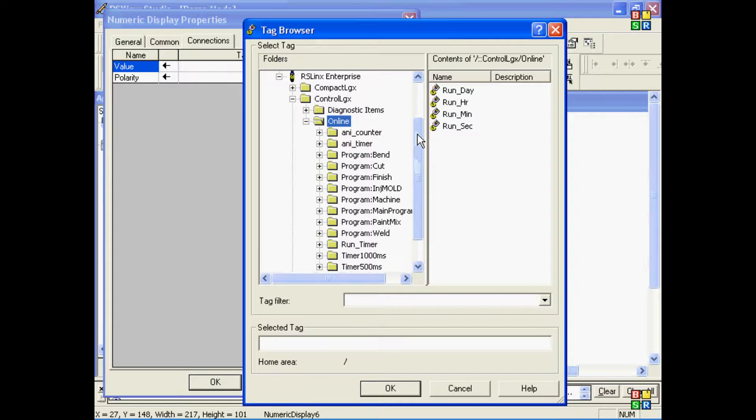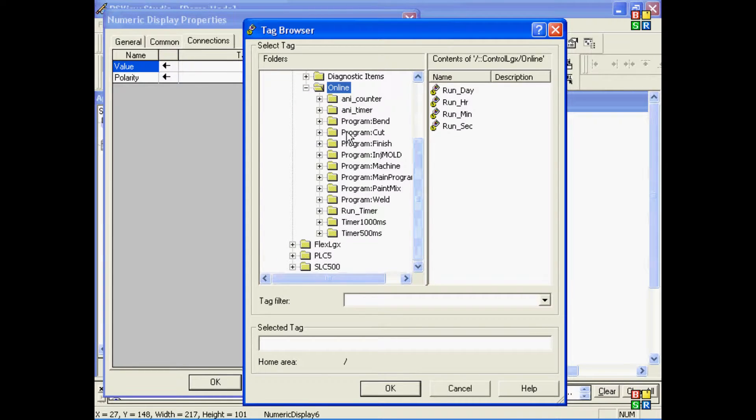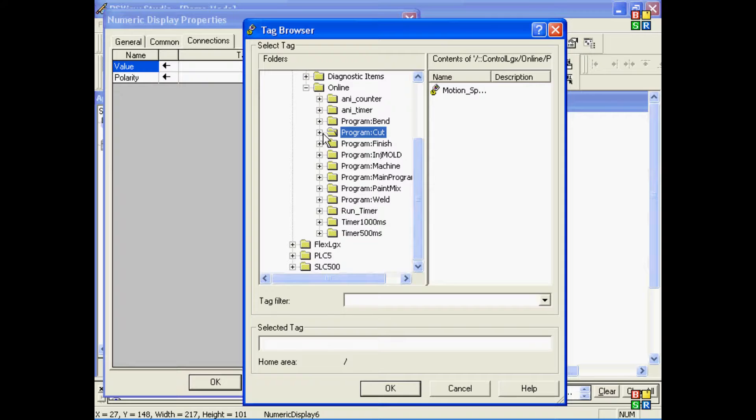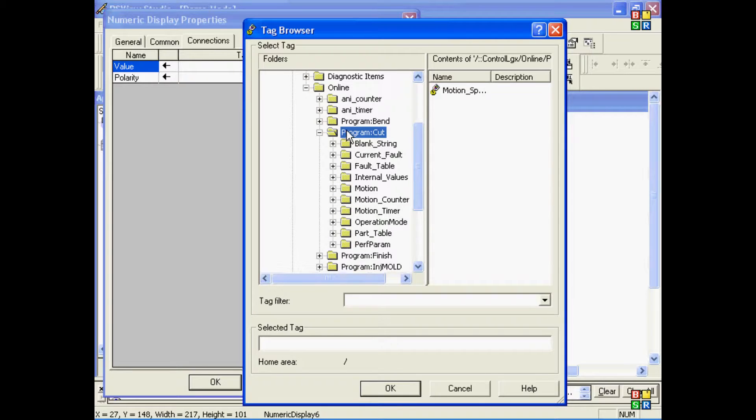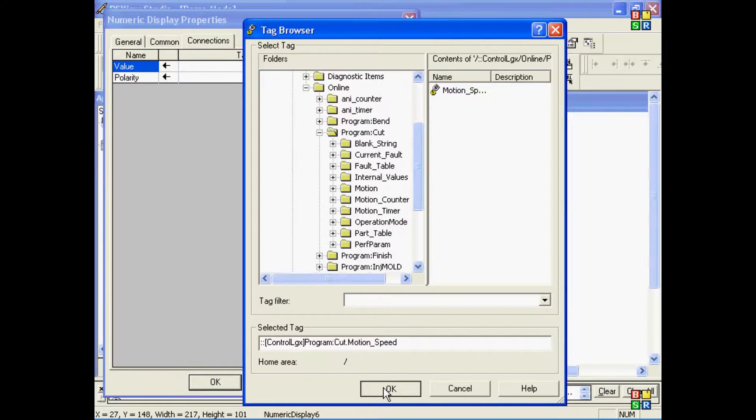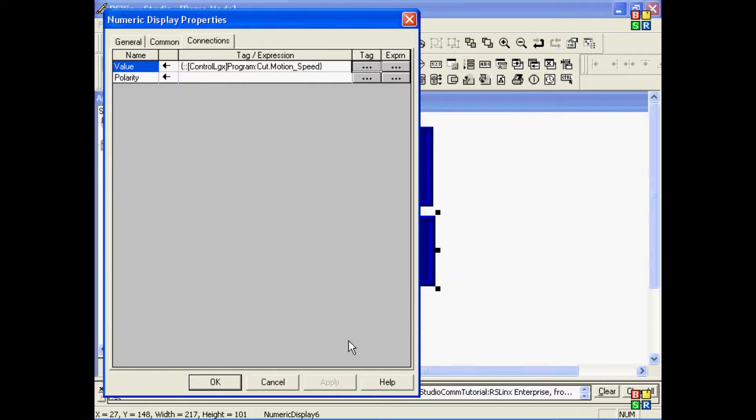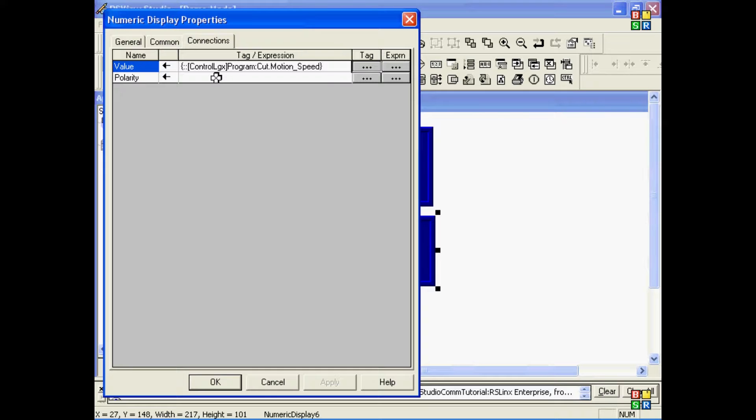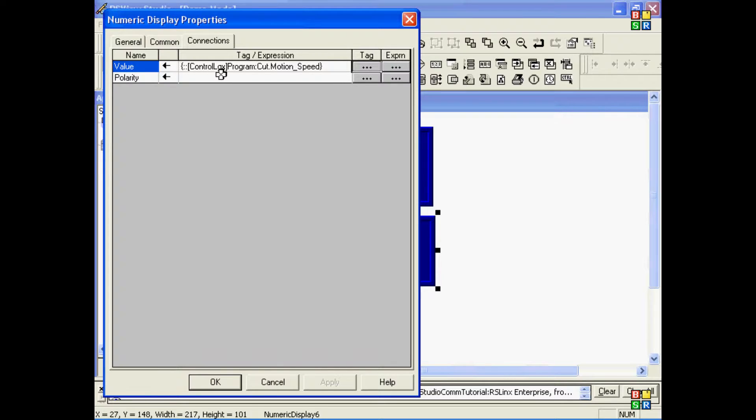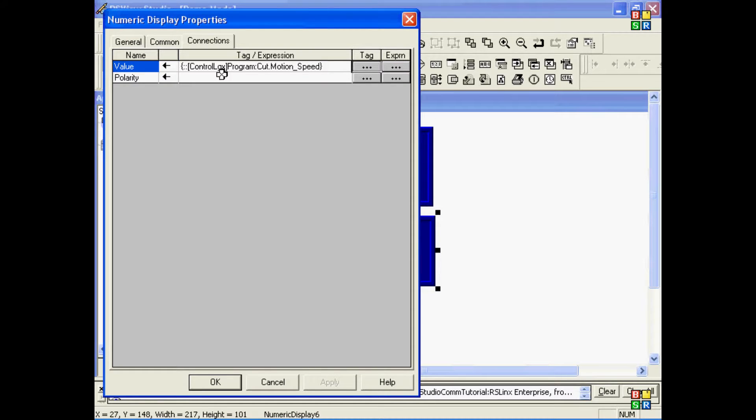In this case, I want some program tags, so I'll select the program, and I'll choose this Motion Tag. Now, keep in mind, when you directly reference a tag inside of a controller to a value on an object, the address will include the shortcut name. So you don't want to go back to RSLinx Enterprise and change the shortcut name later. Otherwise, you'll have to go through all your objects on your screens and update those shortcuts manually.